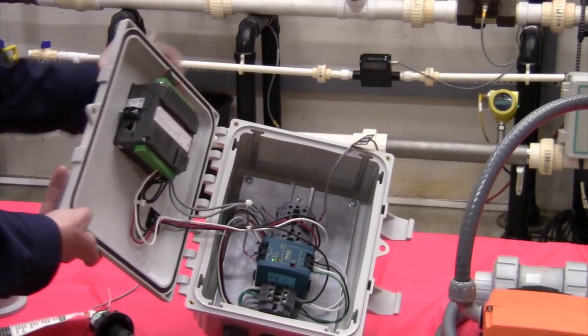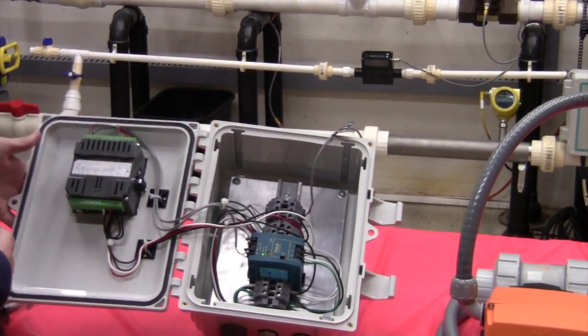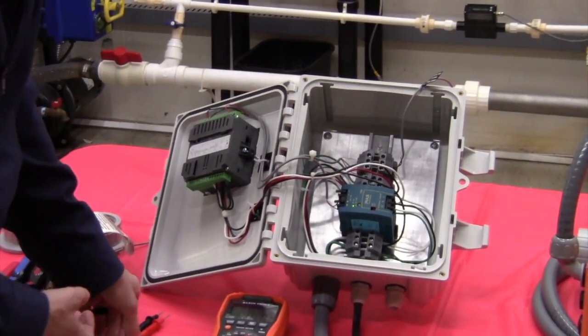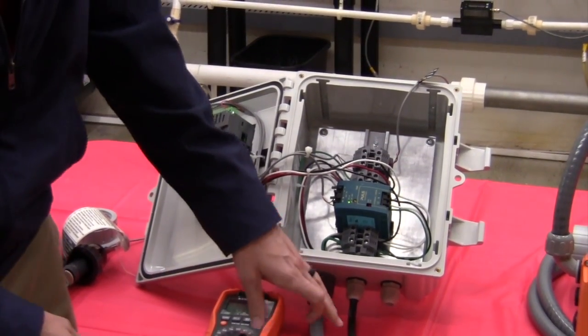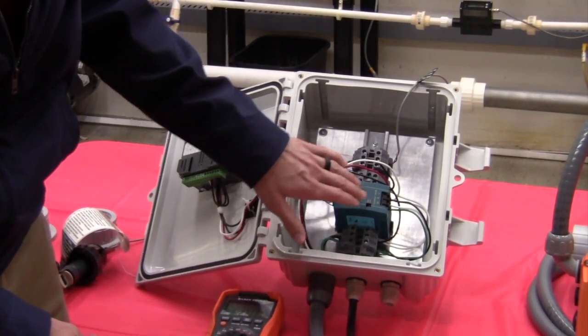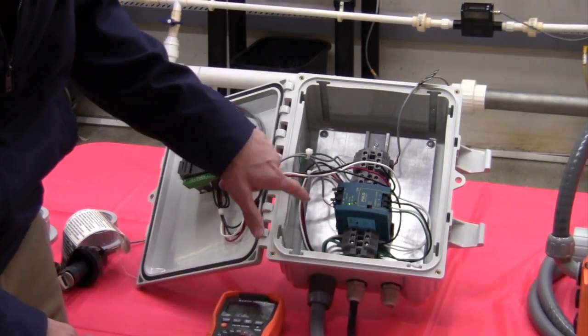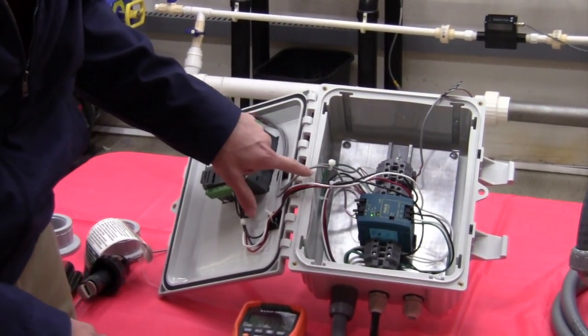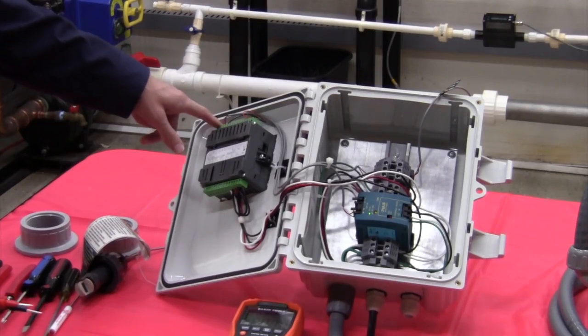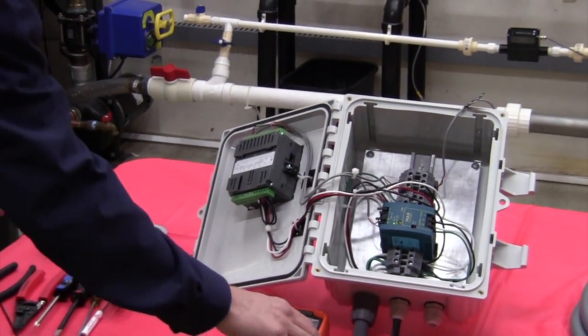Now the next thing that we want to test is the power supply. Again, we have my power cable plugged in, so I've got 120 volts coming into the power supply. Coming out of the power supply is 24 volts DC. Those wires land on terminals 1 and 2 up here.